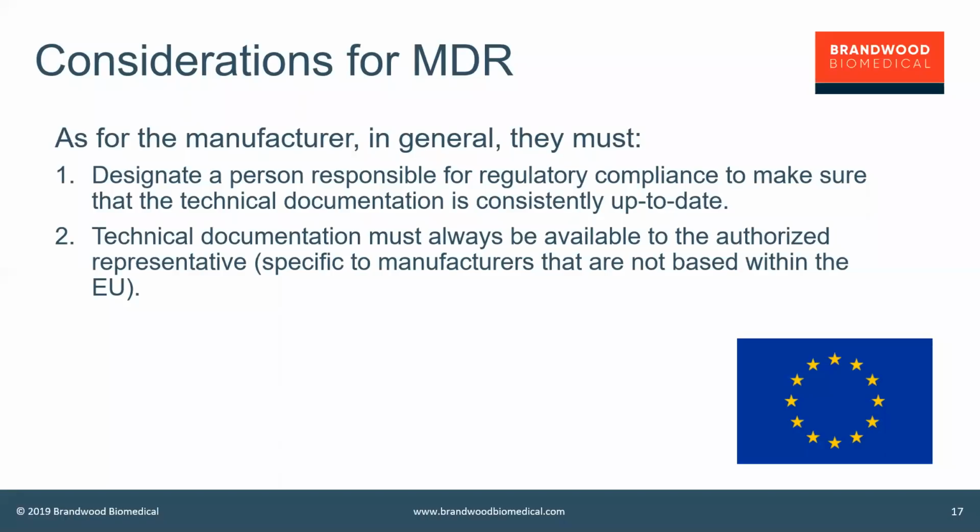Okay, so again, you are still the one who dictates the documentation that gets put into the technical file, but it does create challenges because as you update documents in your technical file, you need to make sure that that's communicated to your authorized rep, and that's something we haven't done before.